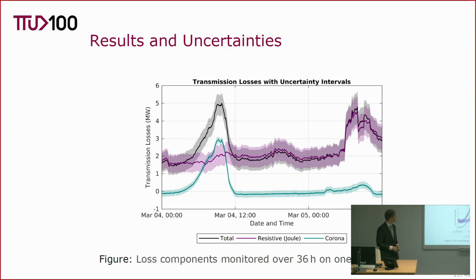Here we can see an example where I have calculated the total losses, Joule losses, and corona losses, and their uncertainty intervals. One important thing to note here is that in some cases we can see these small negative values in corona losses, which is mostly due to the systematic errors from the measurement devices propagated into the estimates of corona losses. So when we're applying it on transmission line, we have to fix this systematic error or bias.